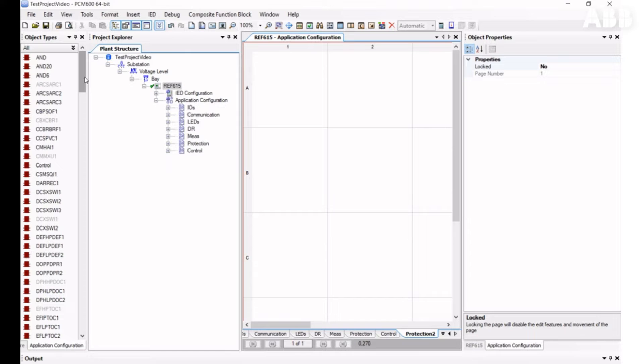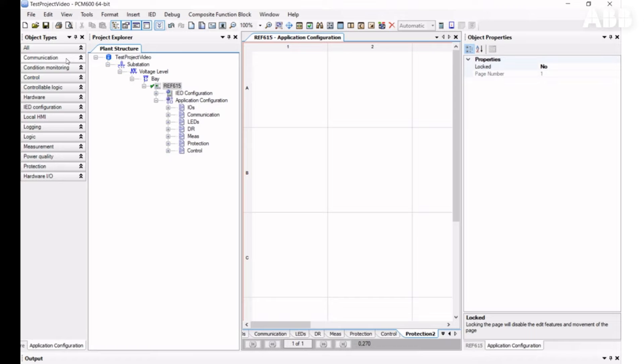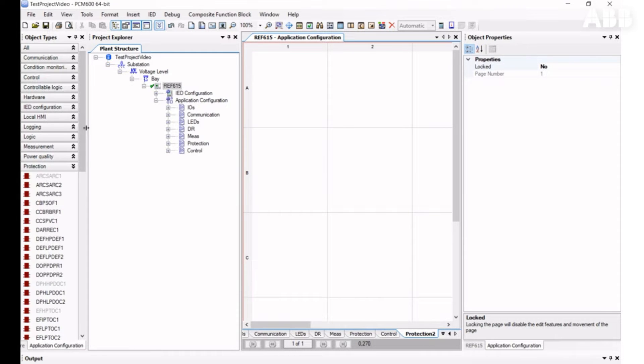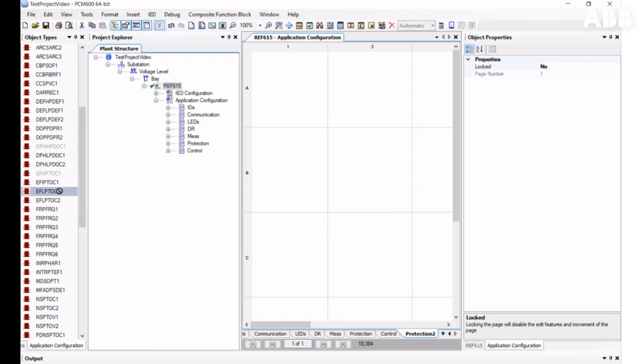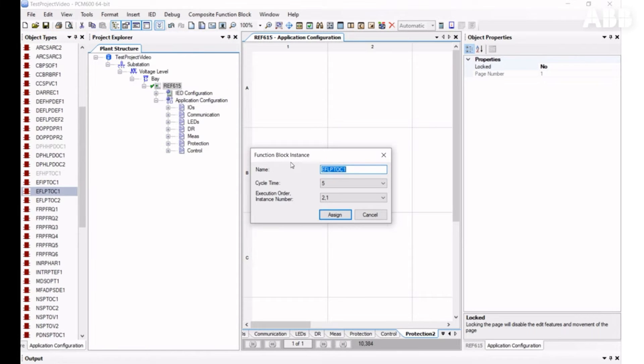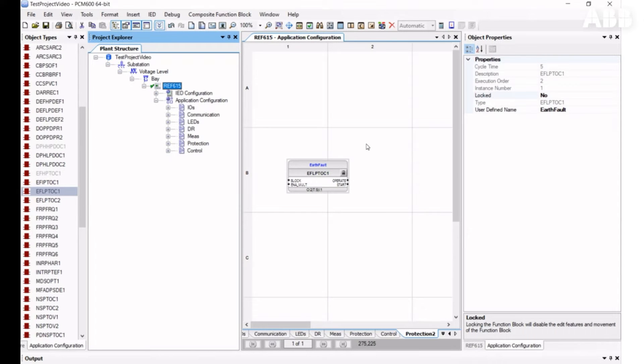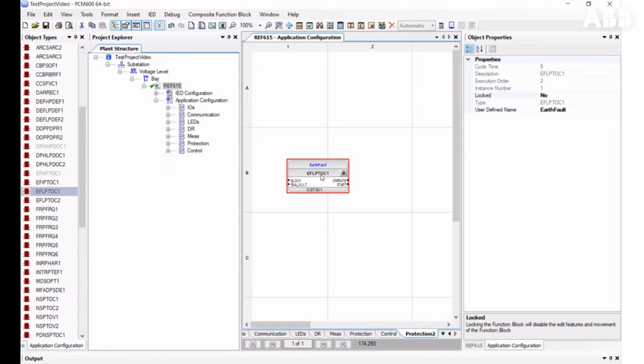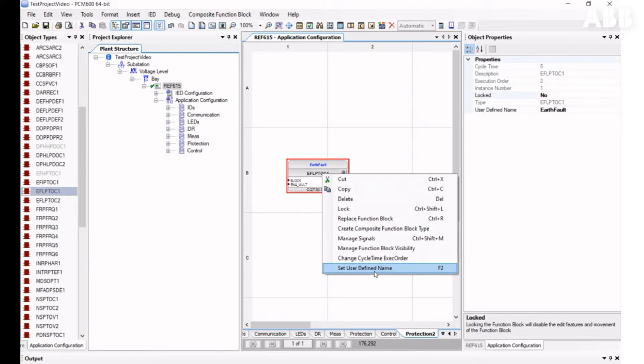Some function blocks are gray and some are not. If the name of the function block is gray, it means it is already used in the configuration, and most function blocks can't be used twice in the same application. When you insert a function block, you can change the name or leave it as default. If you change the name, the user-defined name will be shown on the top of the function block. You can always change the name afterwards by right-clicking on the function block and selecting Set User Defined Name. This name is shown only on the PCM600 interface, not on the Relay Local menu.